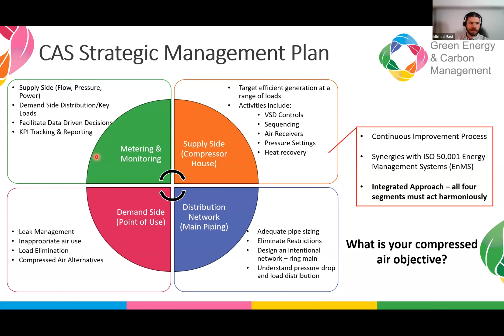So here we've just got a basic schematic of a compressed air system, and some basic metering. There's a power meter on each compressor, and then we've got a flow, pressure, and temperature sensor on the outlet of the compressor house, so the supply side. Now there are many different ways you can do the metering - some people like to have flow per compressor, but for energy management, I've found that 80-90% of applications, it's more than suitable to have a metering configuration like this one. It really comes down to what your objective is as well.